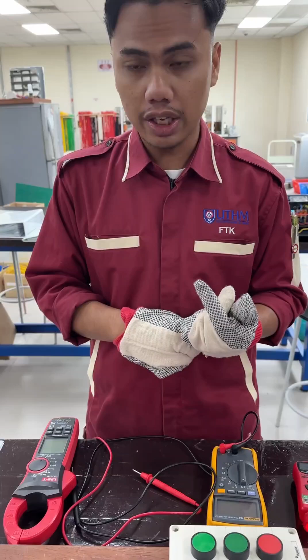I want to teach you how to measure the line voltage of the incoming power supply and the line voltage of the incoming motor, then the phase voltage, current, inrush current, and how to check the RPM using the tachometer.